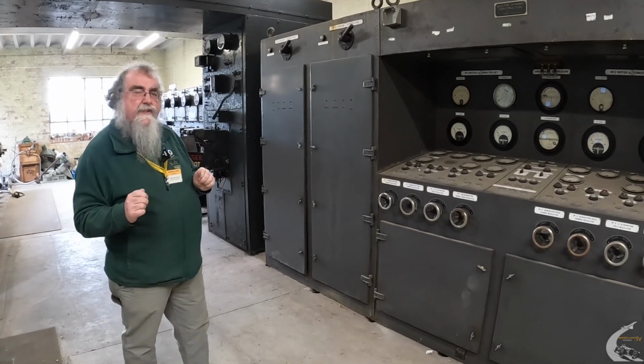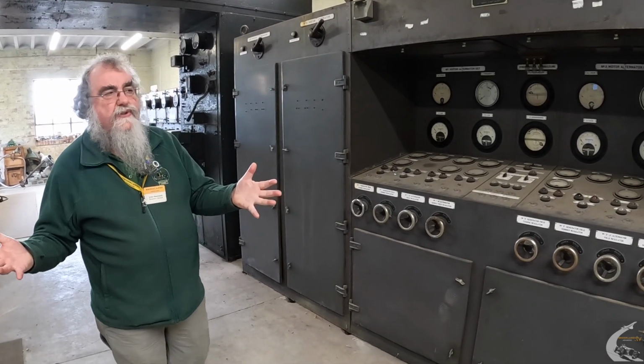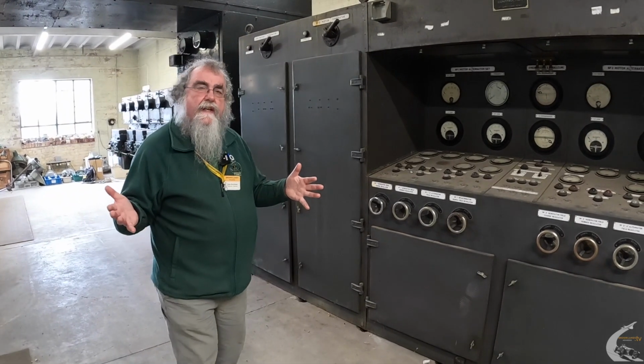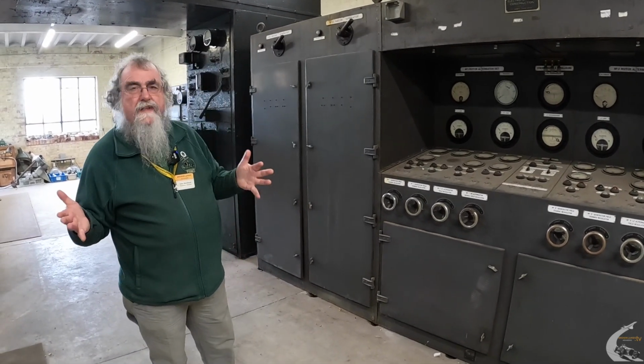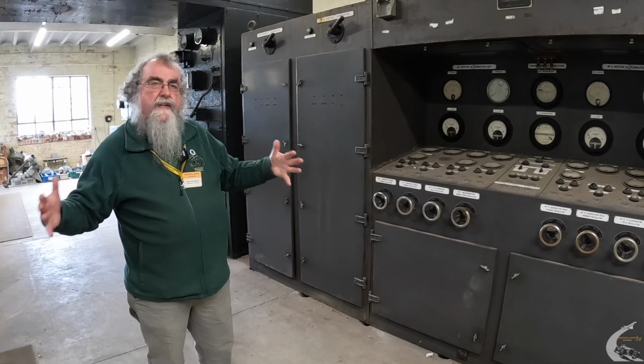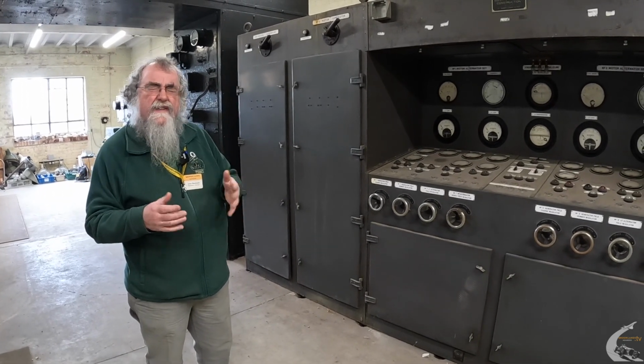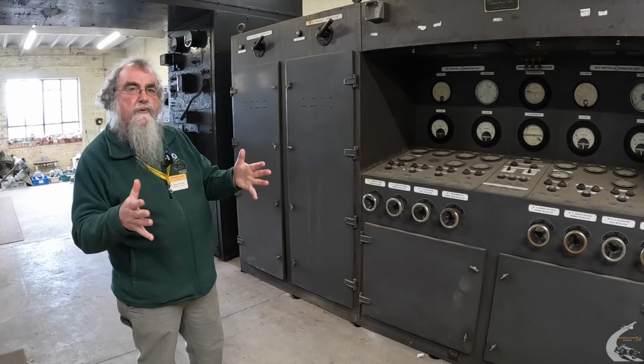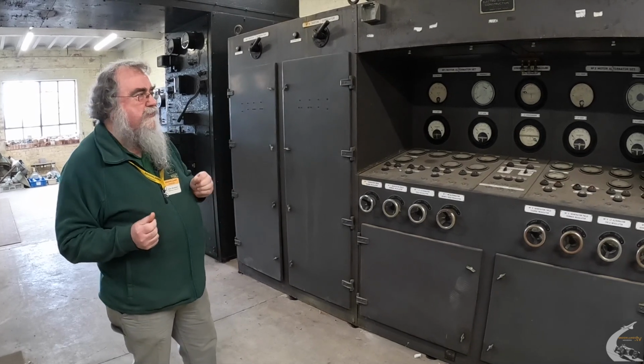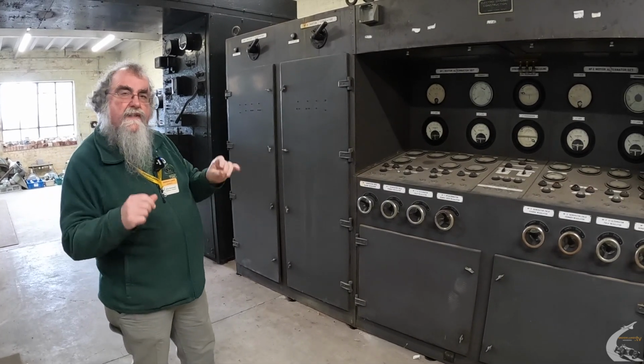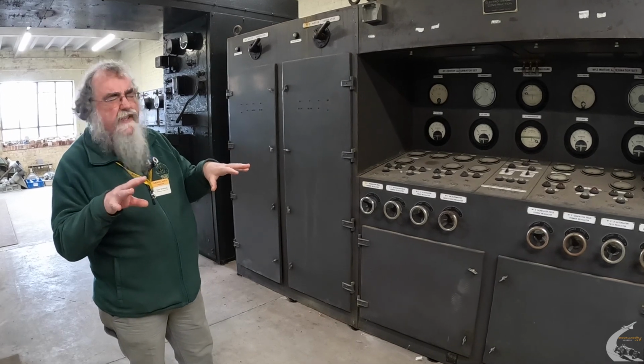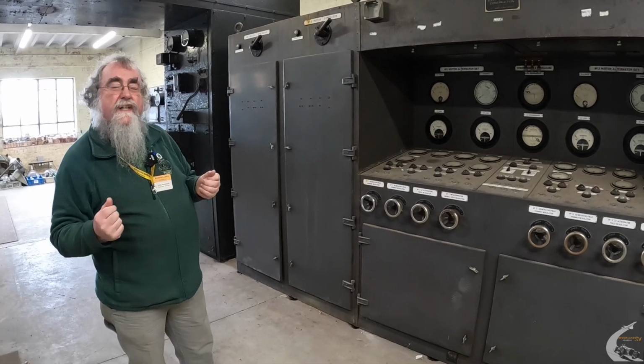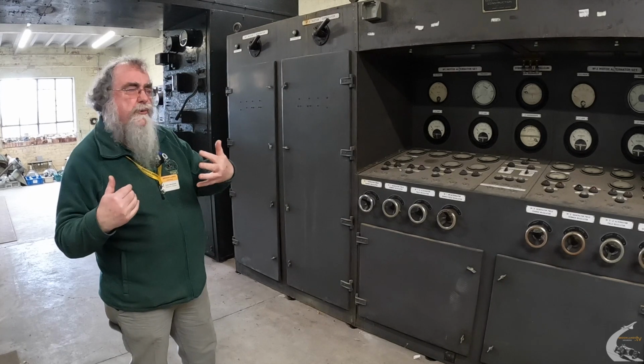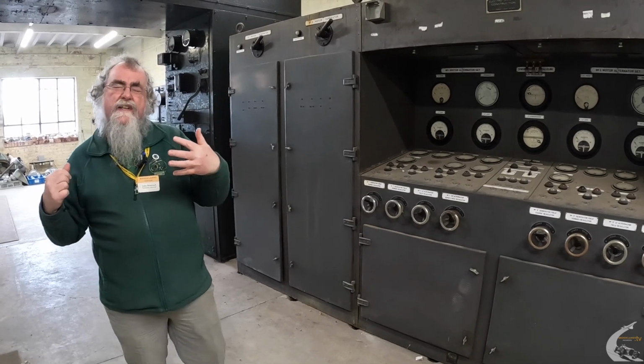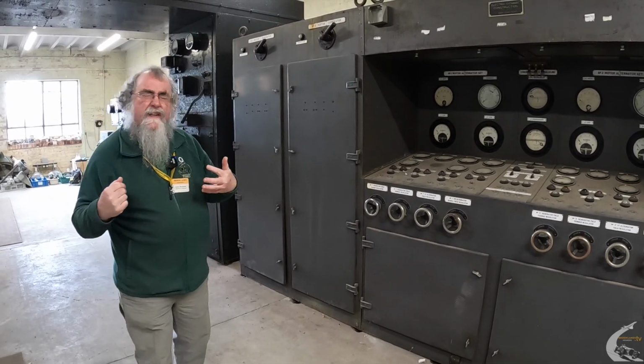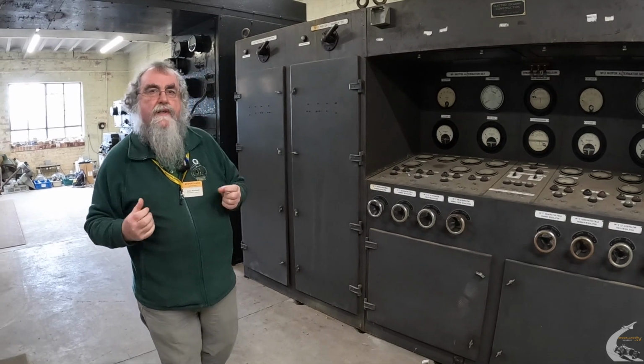Now what you then had is two sources of DC coming off, and they have got quite significant ripple on them. So you need to be able to tie these two together so you can actually provide more DC power. To do that, you have to synchronize the two outputs, or else if you were to join the two together when they're out of phase, you would get a very large bang, flash, and the whole lot would stop working because of the very large current that would occur.